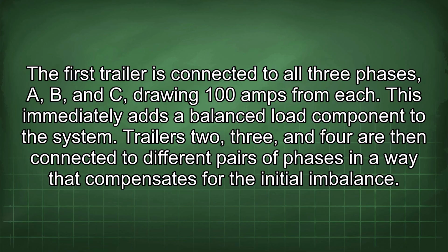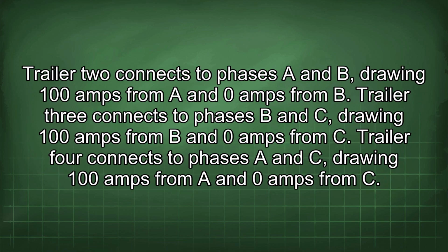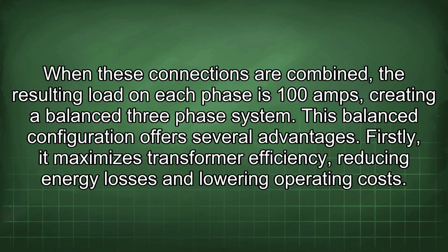This immediately adds a balanced load component to the system. Trailers 2, 3, and 4 are then connected to different pairs of phases in a way that compensates for the initial imbalance. Trailer 2 connects to phases A and B, drawing 100 amps from A and 0 amps from B. Trailer 3 connects to phases B and C, drawing 100 amps from B and 0 amps from C. Trailer 4 connects to phases A and C, drawing 100 amps from A and 0 amps from C. When these connections are combined, the resulting load on each phase is 100 amps, creating a balanced three-phase system.